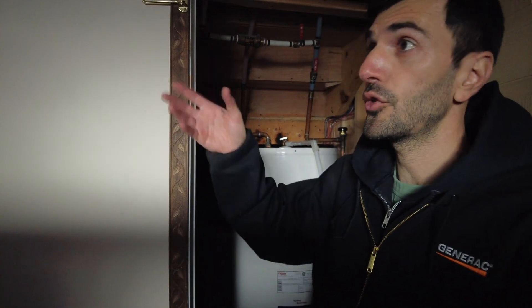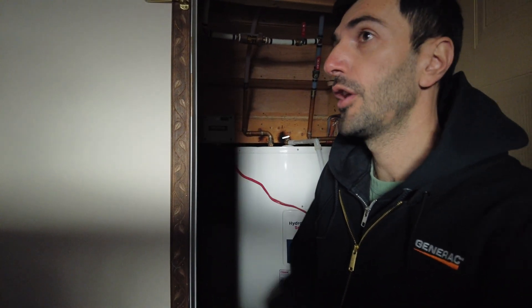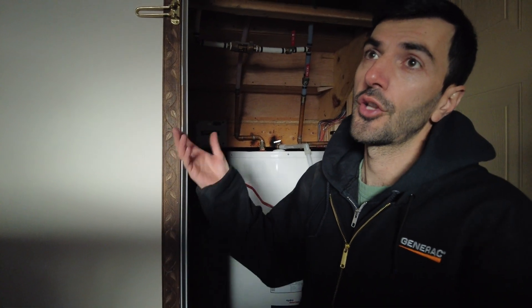So let's say if they put the dryer on, the stove is on, and they put a cake in the oven — then it's going to overload, naturally. The lights might dim. The family will need to be educated that when we lose power, it's not the usual situation — it's not everything as normal. This 26 kilowatt generator gives you 100 amps, which is pretty good, but it's not 200 amps like the main service.